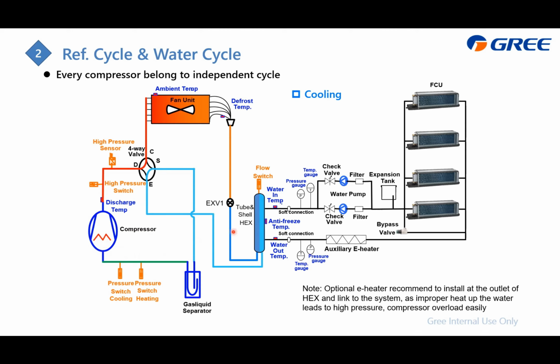And this is for the on-off series. As for the inverter series, we need to change here, which is at the IPM module. The purpose of this is just to cool down the compressor drive, as the compressor drive will release lots of heat. We need to cool it down with the refrigerant. And also add another EXV. These two EXVs here are just to ensure the refrigerant which gets through the IPM module is not too cold. So, this is the refrigerant cycle.